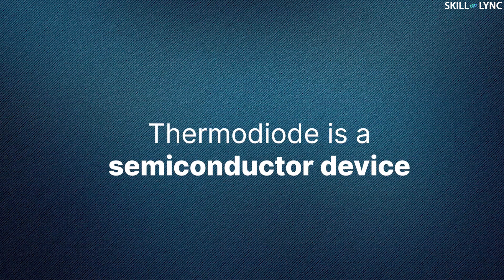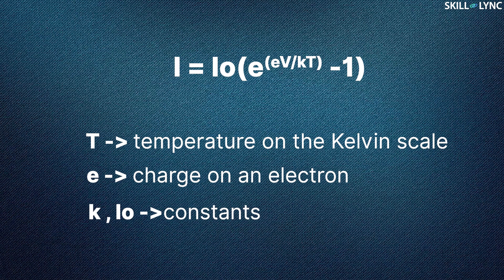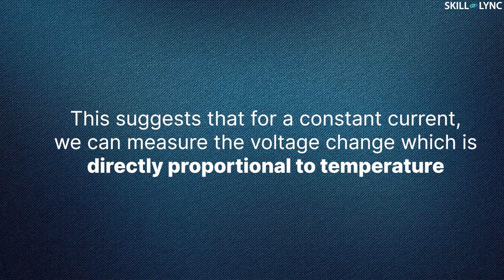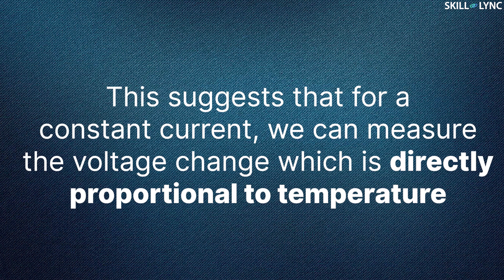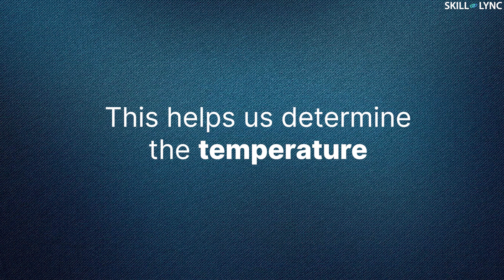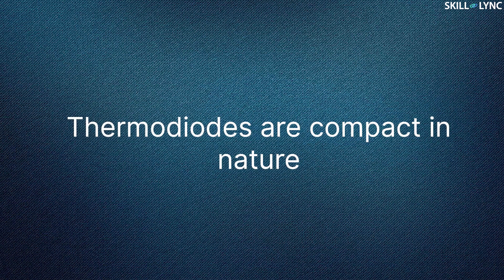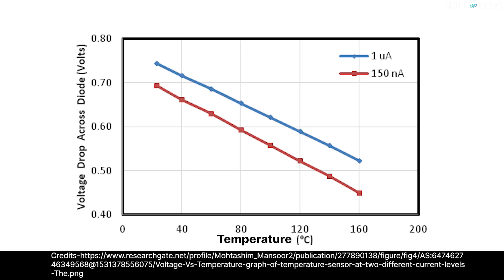The next type of temperature sensor is thermodiodes. A thermodiode is a semiconductor device. A change in temperature in a thermodiode leads to a change in the mobility of the charge carriers, which produces current across the diode. The equation is given here, where T is the temperature on the Kelvin scale, E is the charge on an electron, and K and IO are constants. If the logarithmic value of the voltage is taken, the equation is as shown here. This suggests that, for a constant current, we can measure the voltage change which is directly proportional to temperature, helping us determine the temperature. Thermodiodes are compact in nature and give a graph that is linear in nature.